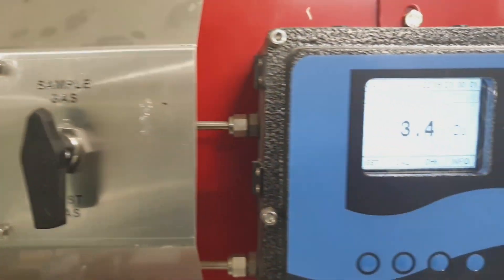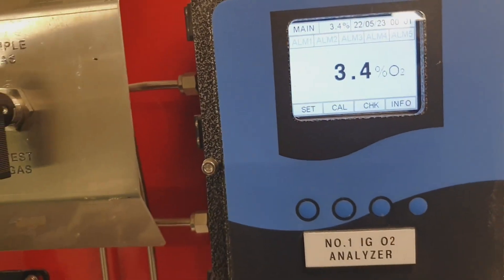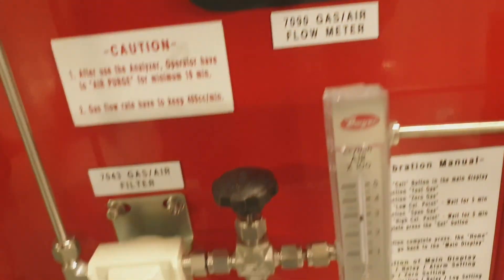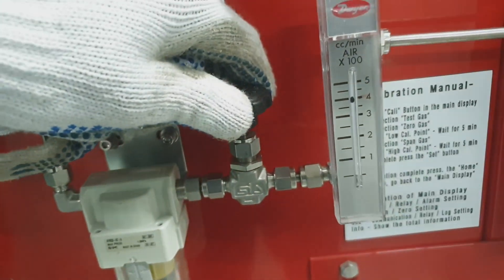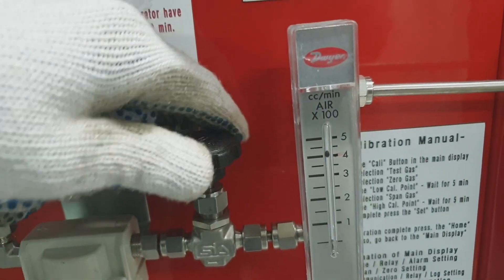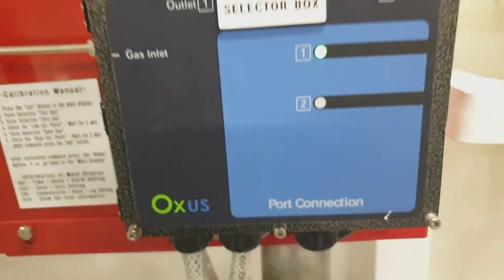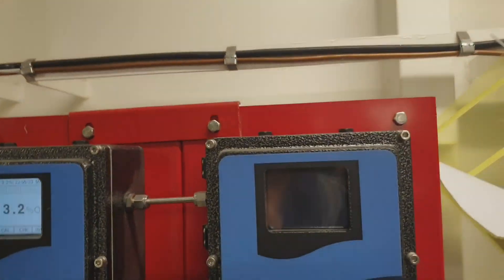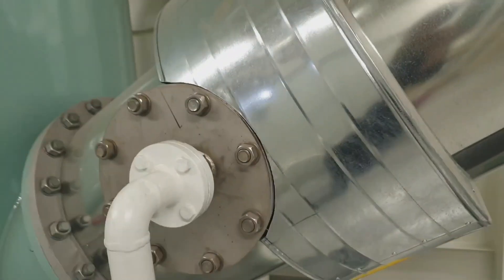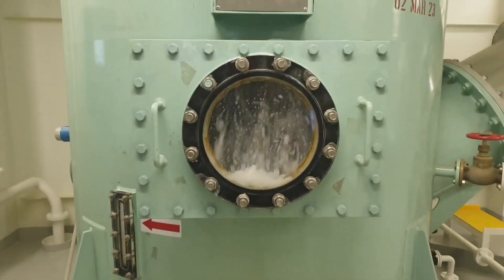As you can see, the oxygen content is 3.4 percent. This is the oxygen analyzer, which measures the oxygen concentration of inert gas. This is the flow control of the inert gas sample. And this is the nitrogen gas for calibration of the oxygen analyzer, together with the compressed air for calibration of the oxygen analyzer. As you can see, this line is coming from the outside valve from the auxiliary boiler.